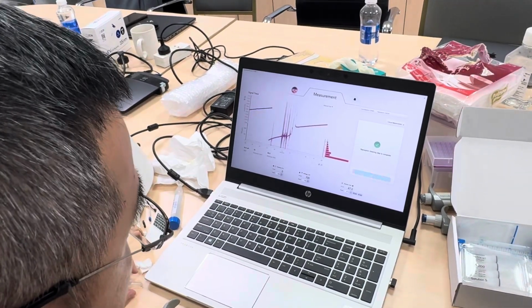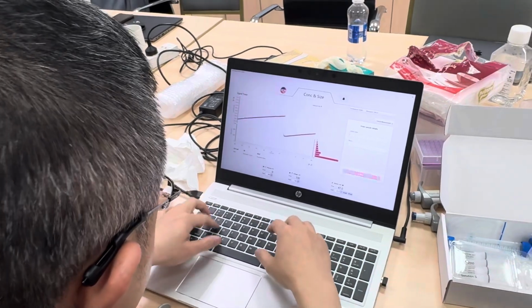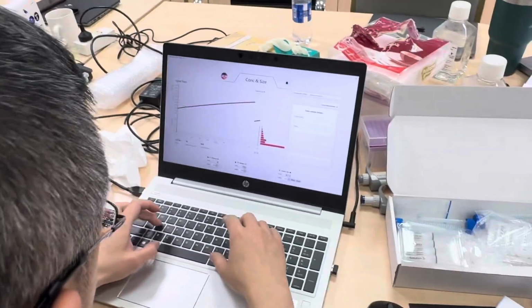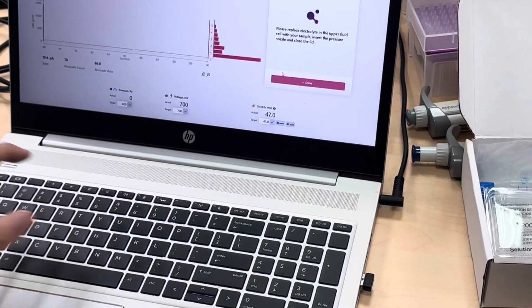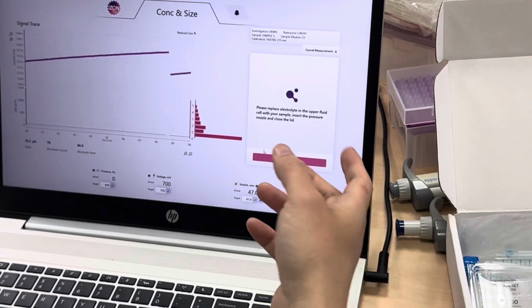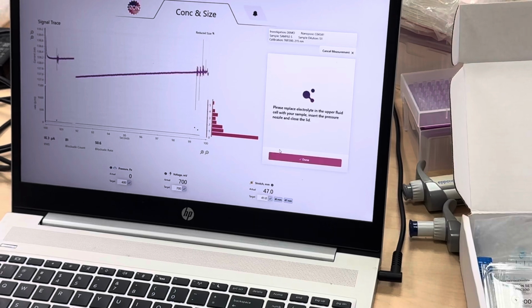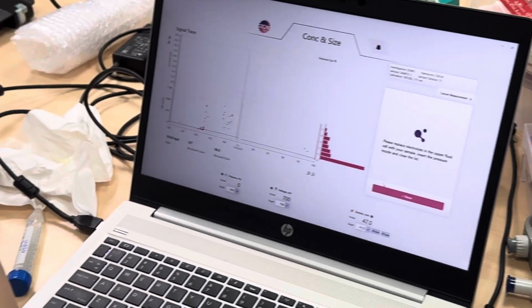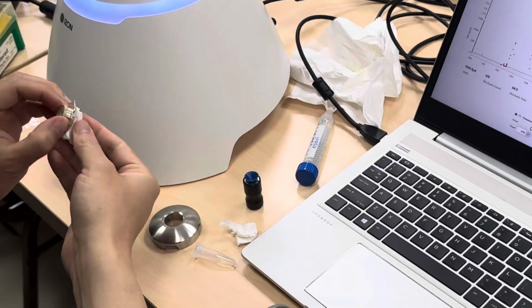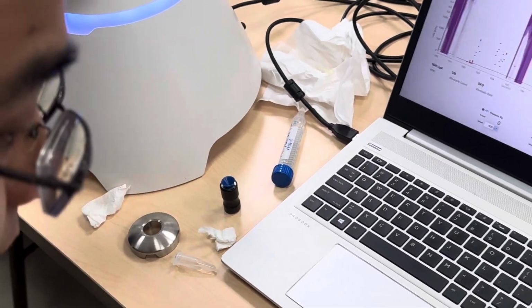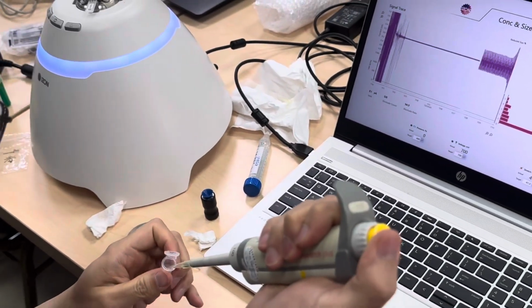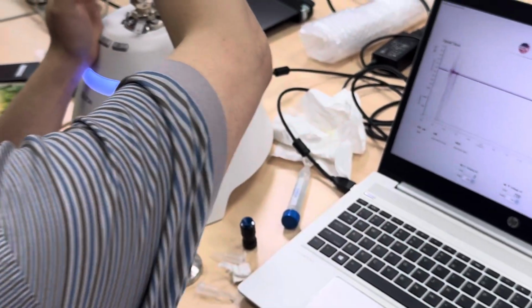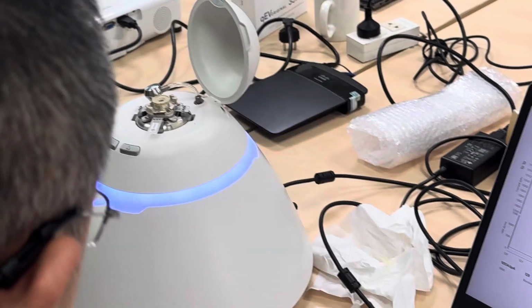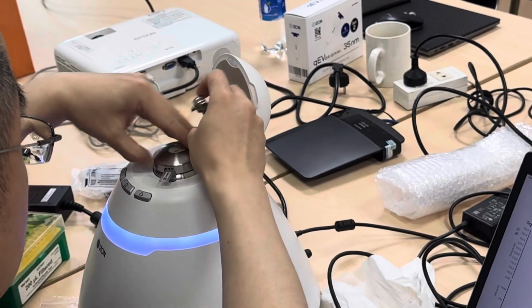Yeah. So we assume it's cleaned now. And now if the nanopore is cleaned, we ensure that one. And then we do the sample S. The dilution is also what we did just now, it's 51 times dilution. Click done. And please replace the electrolyte we just put in with the training sample. We just remove this one and then remove this one. Put it back. And then this one is the sample S. We put it into the sample S, directly to the bottom. And the shading cap, put it back.